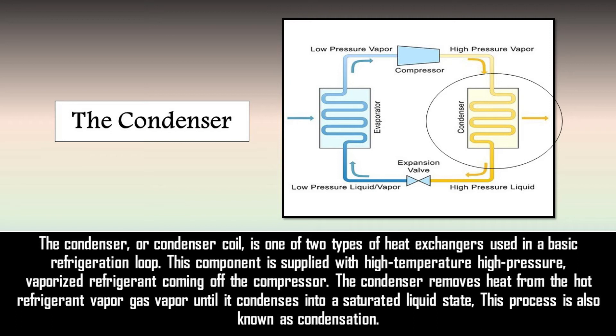Next is the condenser. The condenser or condenser coil is one of the two types of heat exchangers used in a basic refrigeration loop. This component is supplied with a high temperature, high pressure vaporized refrigerant coming off the compressor. The condenser removes heat from the hot refrigerant vapor, gas vapor until it condenses into a saturated liquid state. This process is also known as condensation.